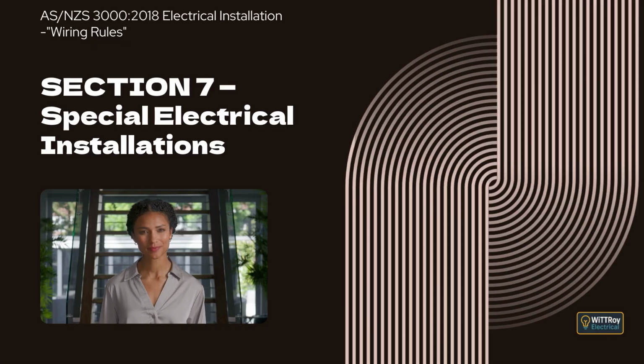Clause 7.2.4.1 General. This clause explains that every safety service must be controlled by a main switch that is separate from main switches used for any part of the general electrical installation and also separate from main switches used for other safety services. The purpose is to make sure that a fault on one safety service does not cause loss of supply to other safety services, and that a fault in the general electrical installation does not interrupt power to safety services. It explains that there is no limit on how many main switches may be installed to control safety services if needed. It also explains that an automatic transfer switch may be used as a main switch, provided it meets the requirements of Clause 2.3.3. The clause further explains that fault current limiting devices used to protect safety services must not be used to protect any part of the general electrical installation.